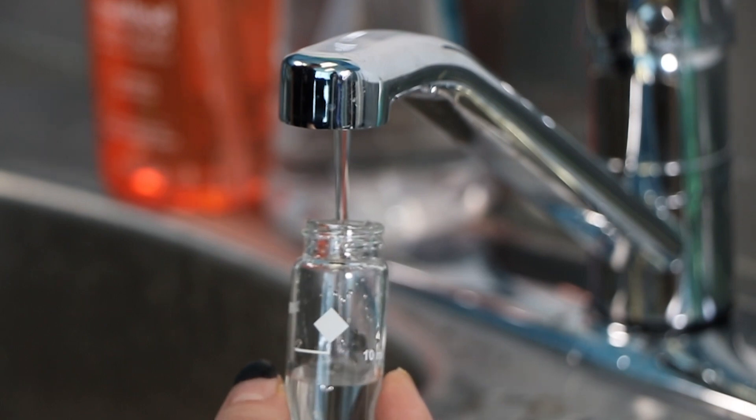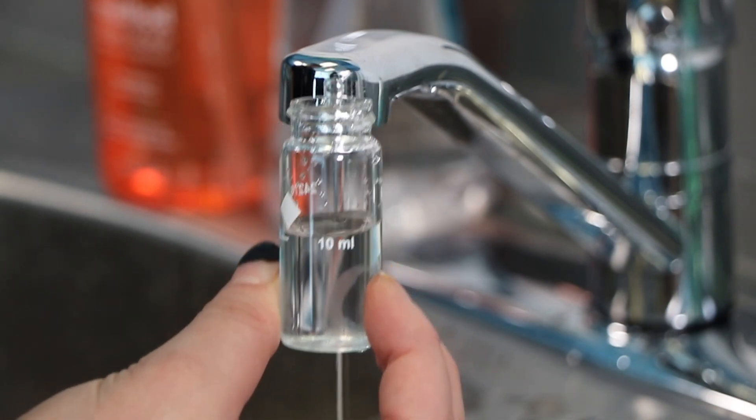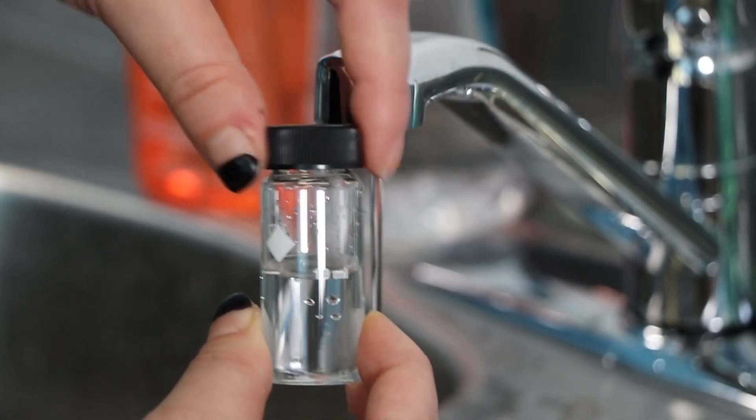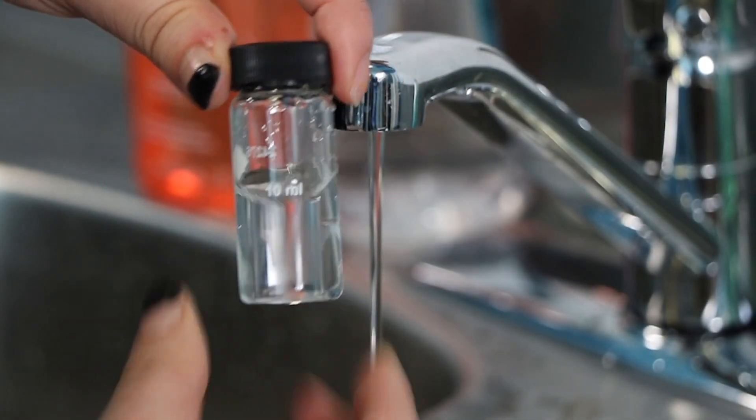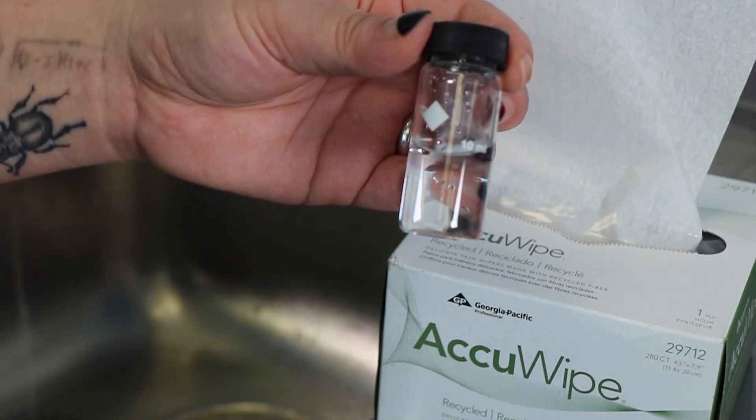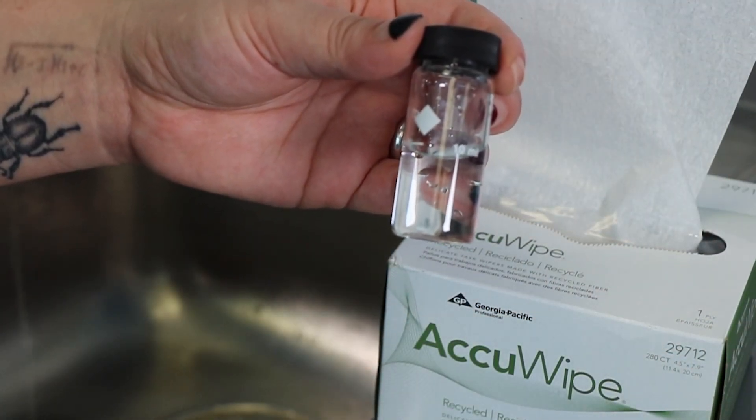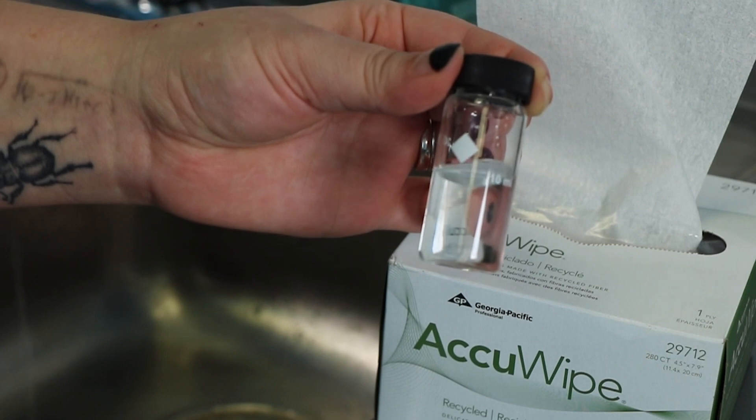Fill the sample cell, also called a vial, to the 10 ml mark and put on the cap. Carefully dry the outside of the sample vial with a lint-free cloth or tissue like an AccuWipe to remove fingerprints and any traces of liquid. Here's a tip: be careful not to scratch the outside of the sample vial as this can affect the reading.